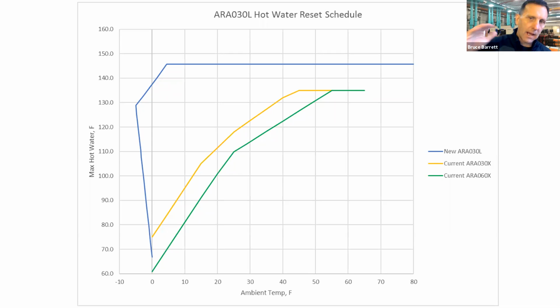145-degree hot water is the absolute max under ideal conditions. But again, if I go back to the study of performance, COP, how it impacts our coil sizing and our pressure drop, we can stay within a safe operational map easily around 120, even 130-degree hot water. We want to stay away from the edges. We want that machine to work.